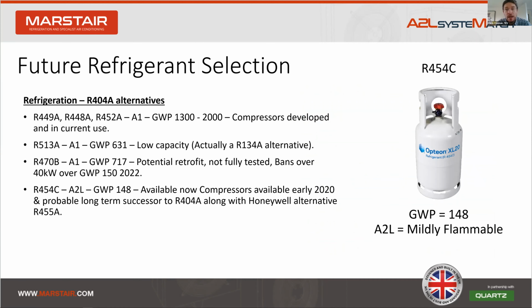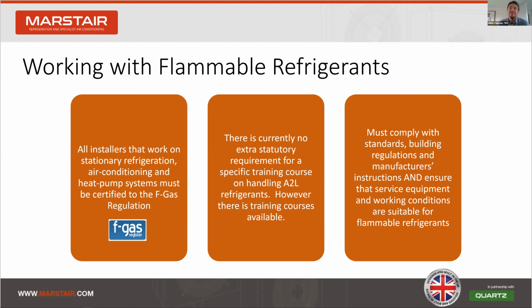So, working with flammable refrigerants, from a regulatory point of view, installers just need an F-gas certificate to buy it and use A2L. However, from a company risk assessment point of view, we would strongly recommend that engineers attend a flammable refrigerant course before using A2Ls. Obviously, it's also important for installers to abide by the regulations and follow manufacturer's instructions.